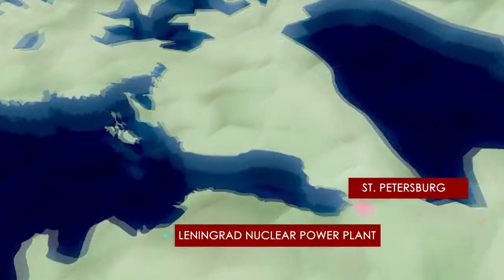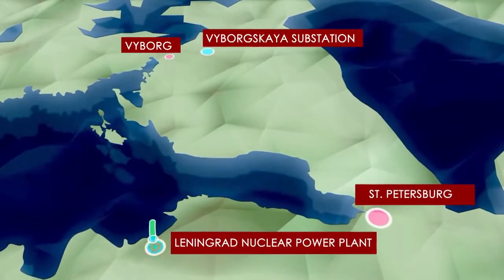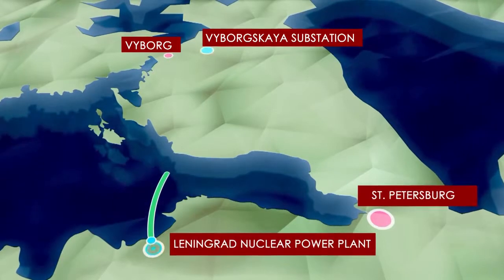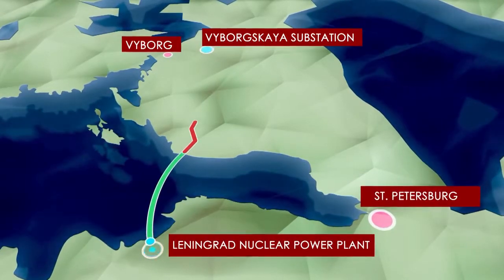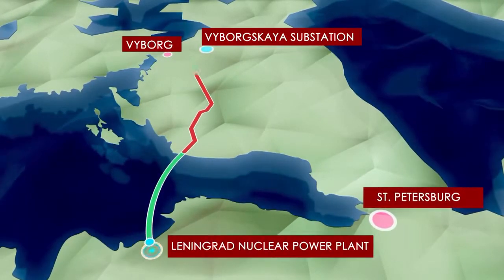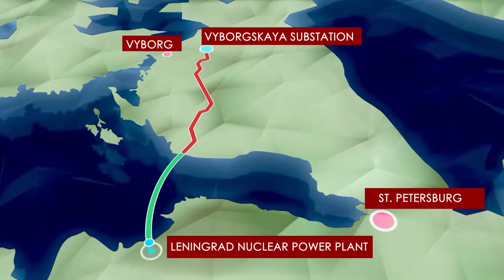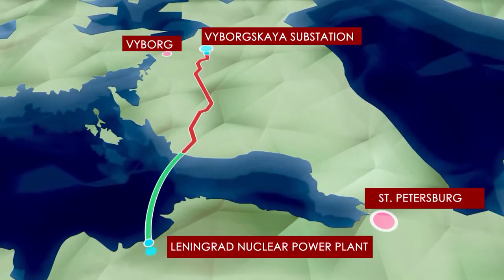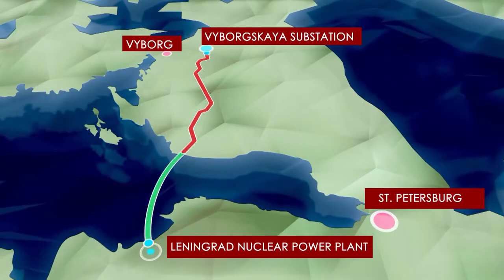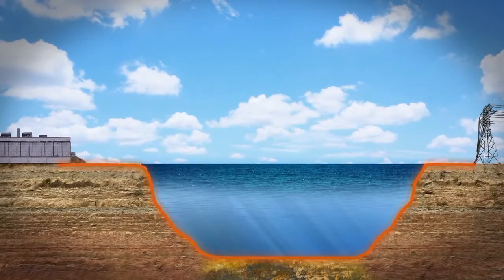A section connecting the converter station and Leningrad NPP will be 5.5 km long. Overhead power transmission line laying and submarine cable line laying will each take half a year. The submarine cable line section, rated ±300 kV, is 47 km long, running from the converter station to the northern coast of the Gulf of Finland.